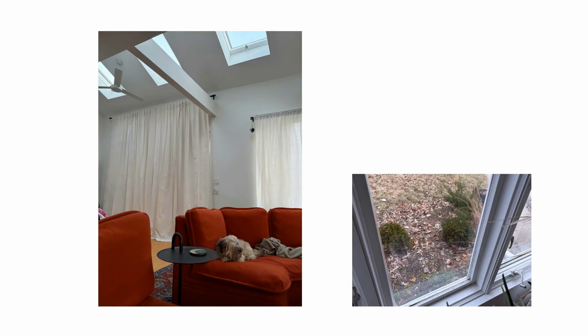So if you are working on a renovation where you do have poorly insulated foundations or slabs, or you're not able to get ductwork close enough to the exterior wall, you don't have a lot of supply air, you should think seriously about providing baseboard heat, providing electric heat, doing radiant floors, or providing some other heat source in order to raise the surface temperature of those spaces or of those surfaces so that you can avoid condensation in those cases, so that you don't end up with something like this.